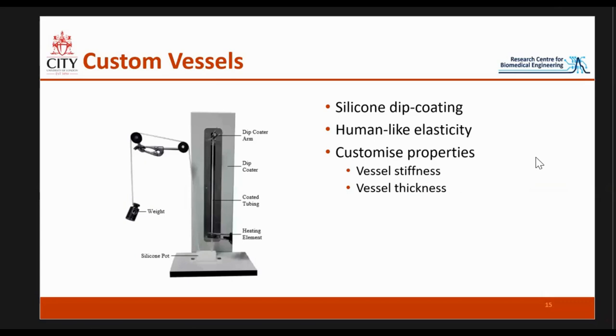This is how we do it using a dip coater. The job of this device is simply to move an arm up and down. We have a silicone pot at the bottom where we put our silicone mixture. We use a form — in this case just commercial tubing — that we dip through the silicone pot, and it slowly, gradually rises up through a heating element. As it rises after being dipped, it will have a silicone coating around the tube. With the heating element and time, it will cure, and we're then able to remove the internal tubing, leaving just that silicone coating, which becomes our new vessel with much more human-like elasticity than traditional rubber tubing.